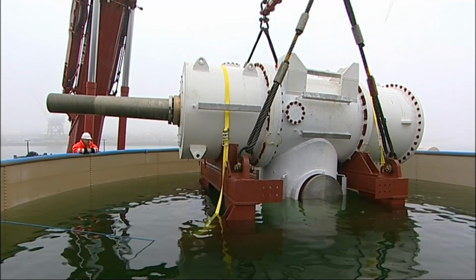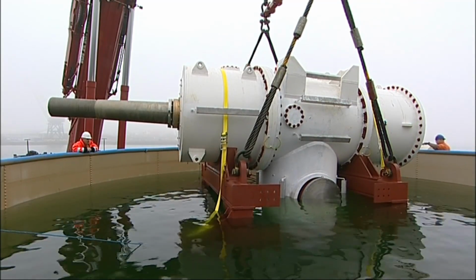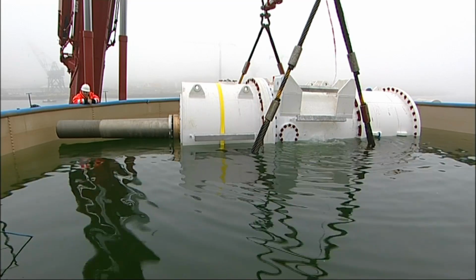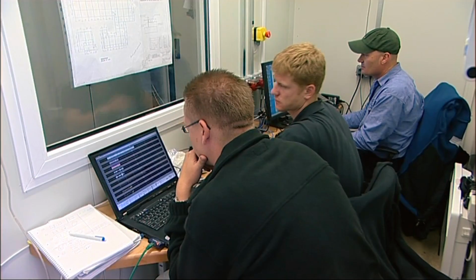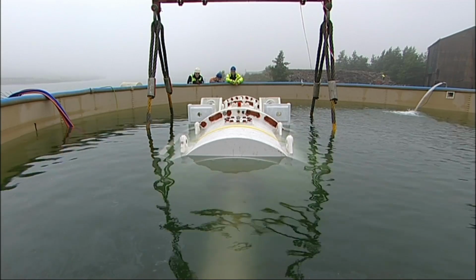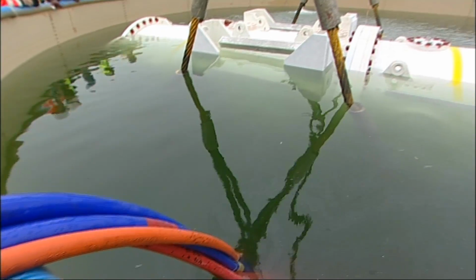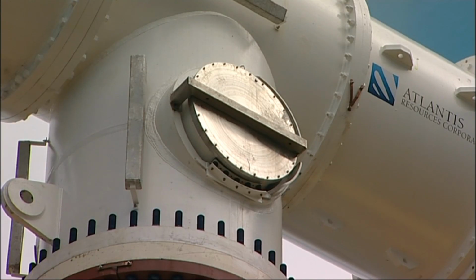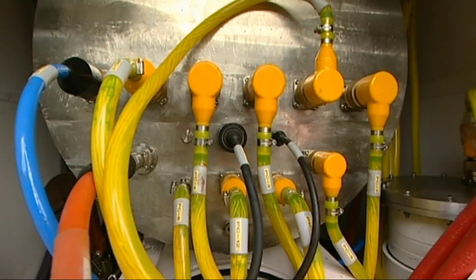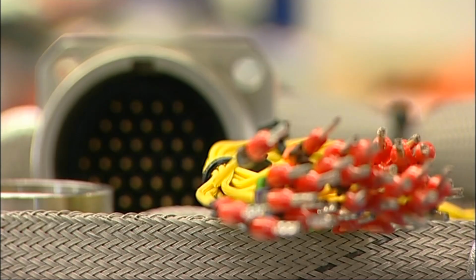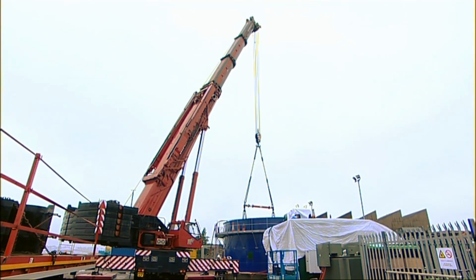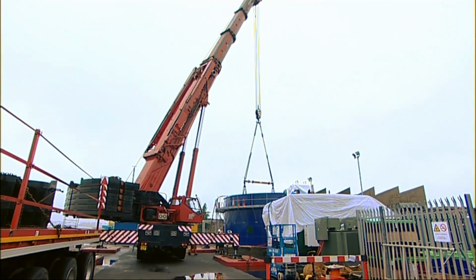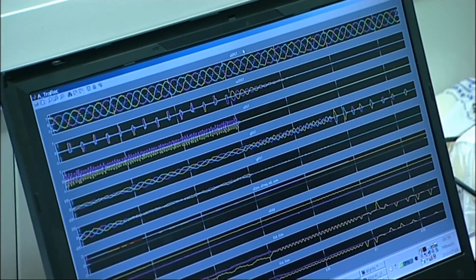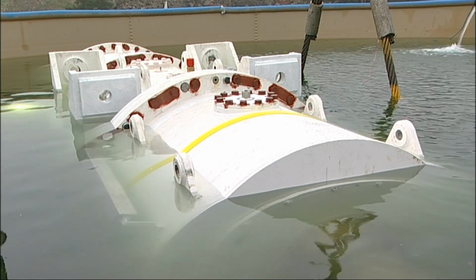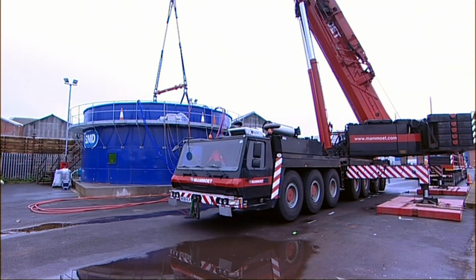All of the electronic components have been tested prior to being fitted into the nacelle, but this is the first opportunity that the team has had to ensure that all of the sensors and the turbine's central computer communicate correctly. Access hatches in the nacelle enable the easy replacement of most electrical components, and the modularized assembly system allows wiring looms to be removed and checked. The turbine is then hooked up to the control room and energized with a 3.8 kilovolt supply. The generator is run in motoring mode, and the powertrain is fired up for the first time.